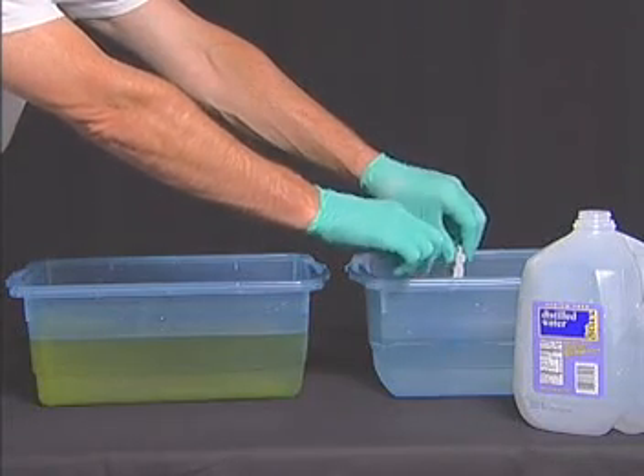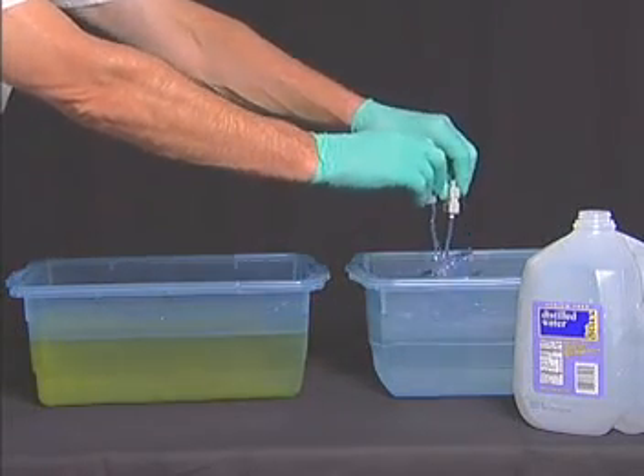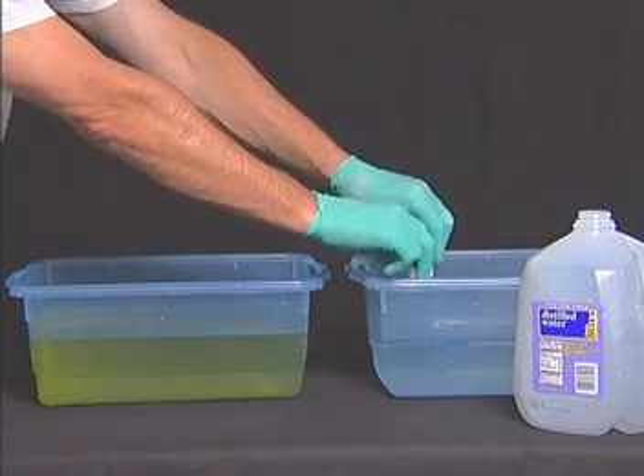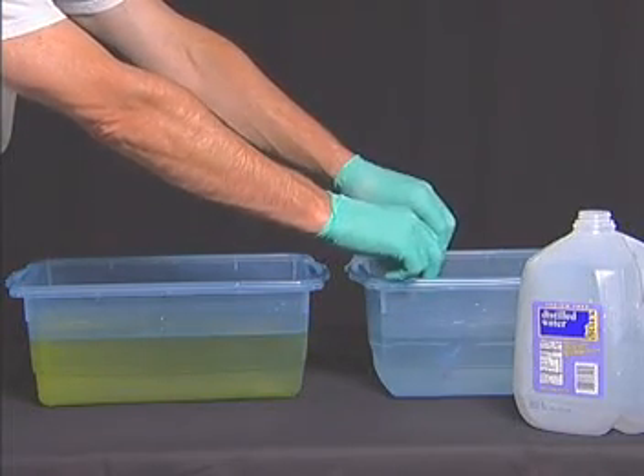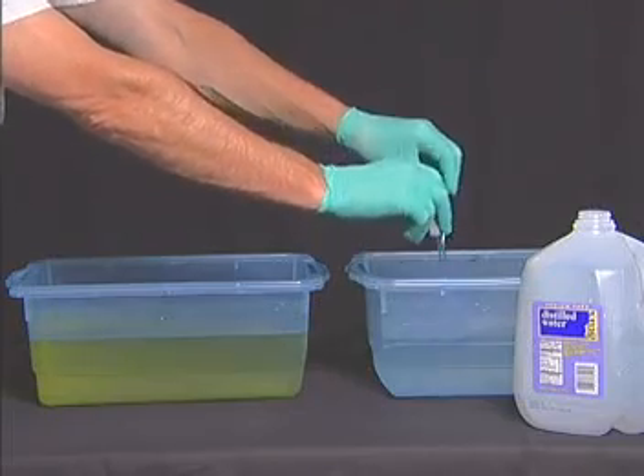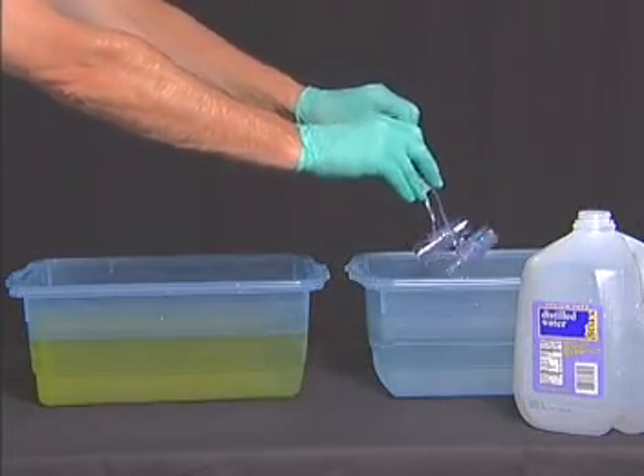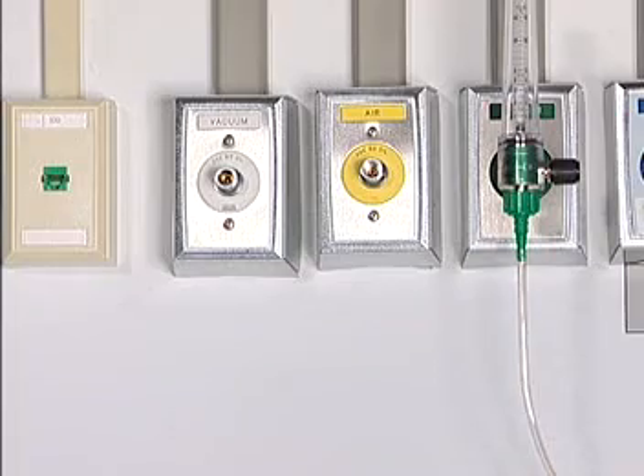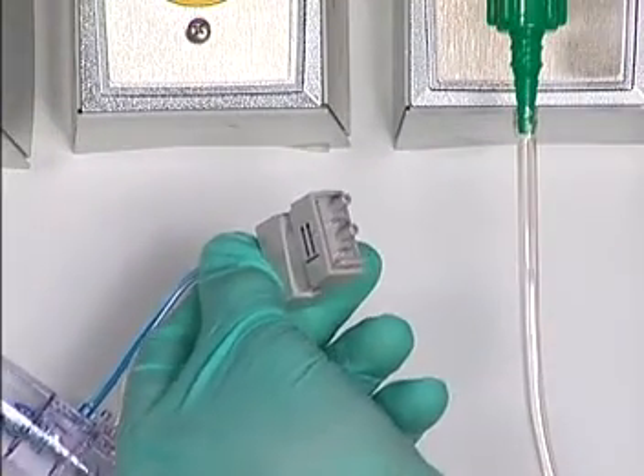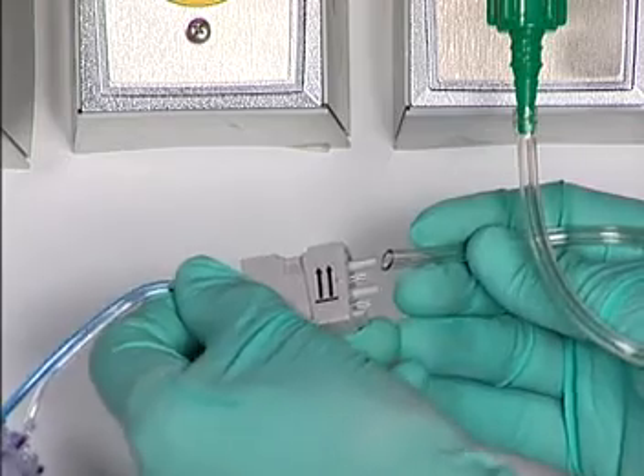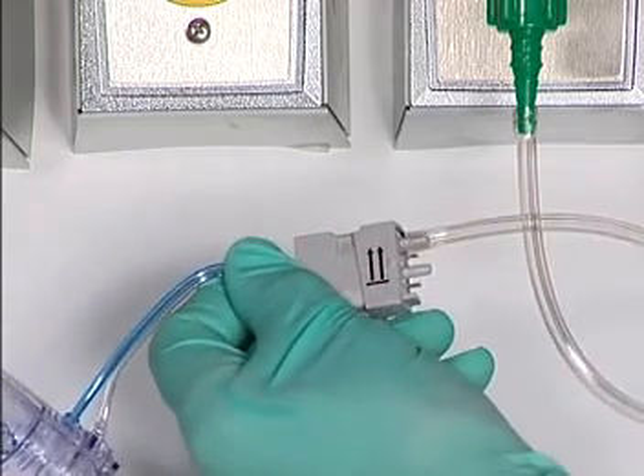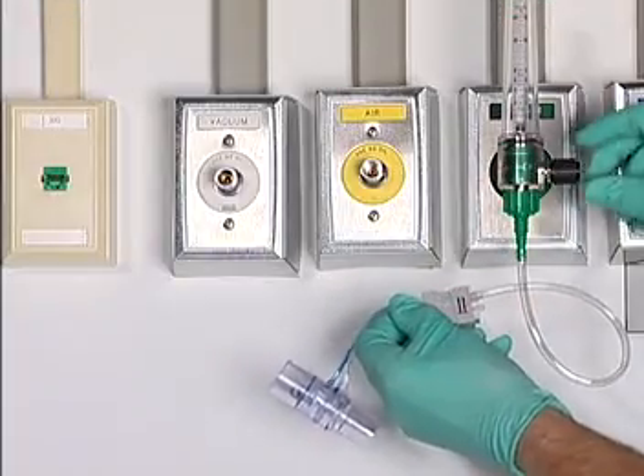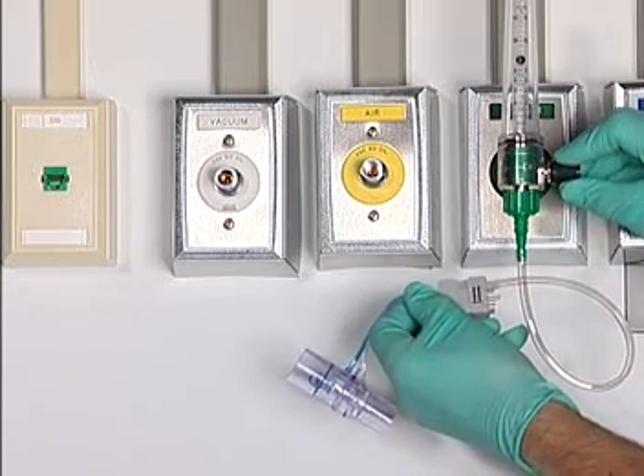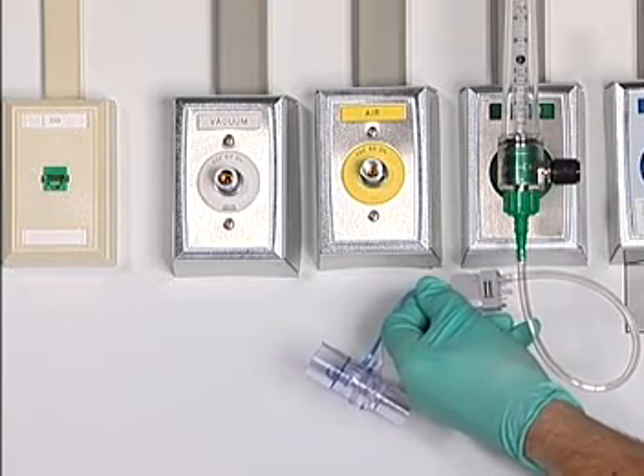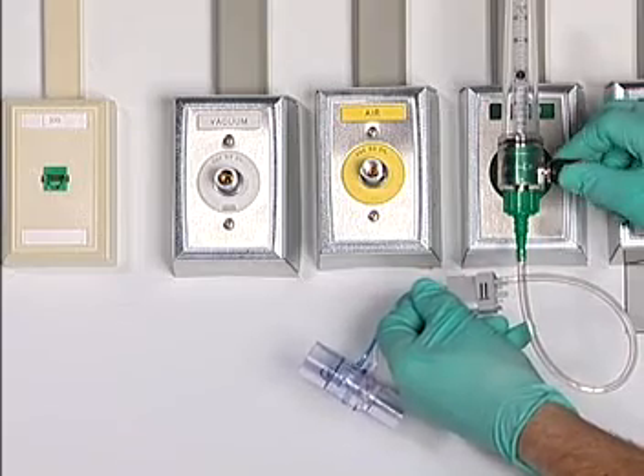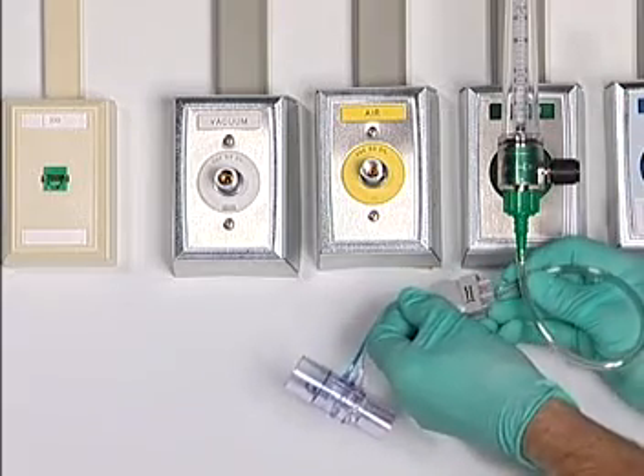Afterwards, submerge the flow sensors and tubes in distilled water. Again, do not get the connector wet. Rinse as indicated in the Cidex instructions. Submerge and rinse several times to remove all the Cidex. Make sure to completely dry the flow sensors and tubes before using the sensors. Please consult your user's reference manual for complete flow sensor cleaning and maintenance recommendations.